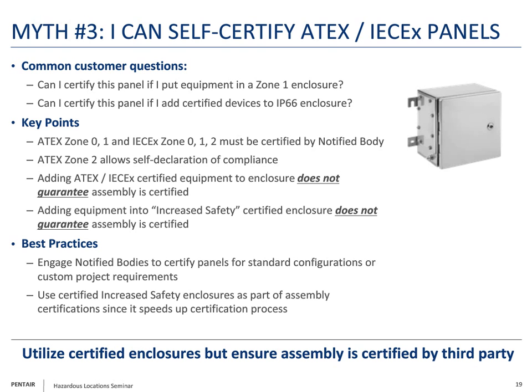So one of the questions we get is, can I certify this panel if I put equipment into a Zone 1 enclosure, or can I certify this panel if I add certified devices into an IP66 enclosure? And the broad answer is really no. In ATEX Zone 0 or 1, or IECEx Zone 0, 1 or 2, you have to have the system evaluated by a notified body. So they have to evaluate your design, evaluate the system, go through the testing, and certify it. The only place where you can do some self-declaration of compliance is for ATEX Zone 2, but you still have to go through all the rigorous testing that's required by the standards.